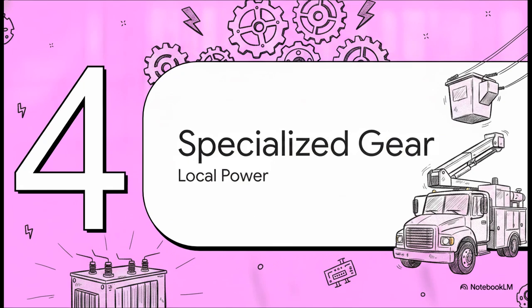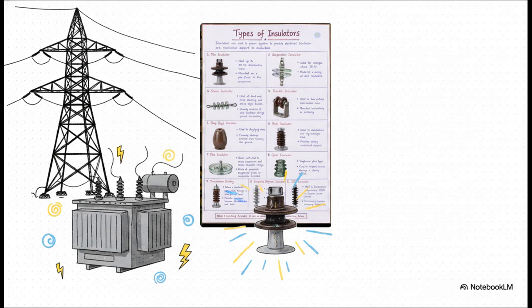Which brings us to part 4, local power and specialized gear. Whenever you see those large metal cans up on poles or those massive ground-level green boxes in your neighborhood, you're looking at transformers. But think about it: how do you get a supercharged live wire into a metal box without electrifying the whole box and blowing it up? That is exactly where the transformer bushing comes in. This highly specialized insulator allows a conductor to pass safely straight through a transformer tank, providing a robust collar of insulation between the live conductor and the metal tank wall, ensuring the electricity does its work inside without turning the whole setup into a hazard.